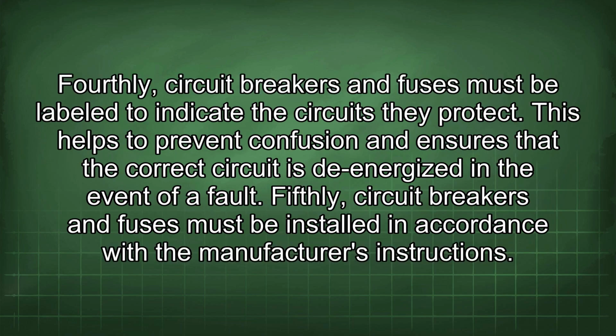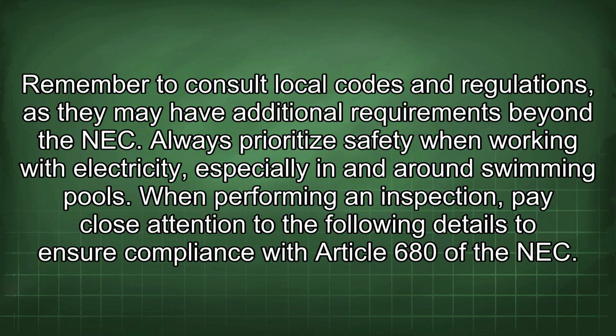Fourthly, circuit breakers and fuses must be labeled to indicate the circuits they protect. This helps to prevent confusion and ensures that the correct circuit is de-energized in the event of a fault. Fifthly, circuit breakers and fuses must be installed in accordance with the manufacturer's instructions. Remember to consult local codes and regulations, as they may have additional requirements beyond the NEC. Always prioritize safety when working with electricity, especially in and around swimming pools.